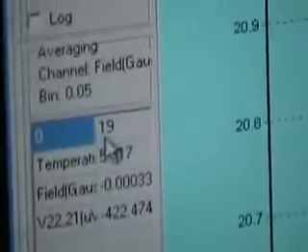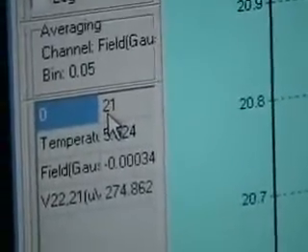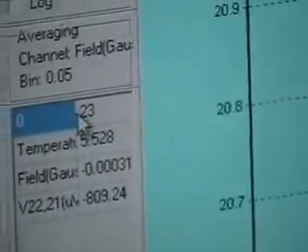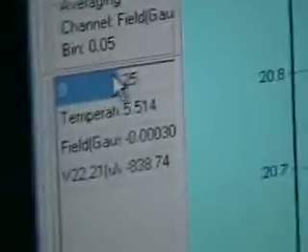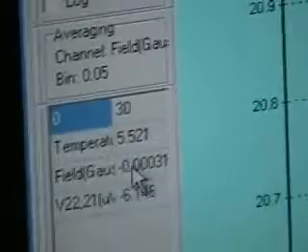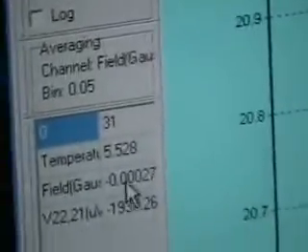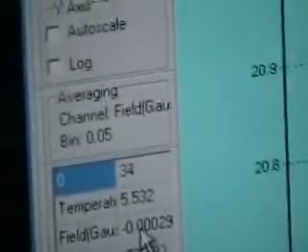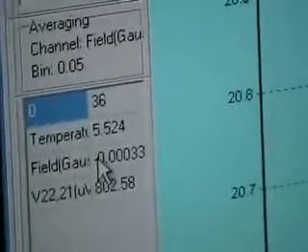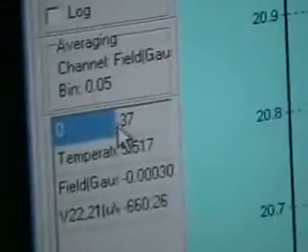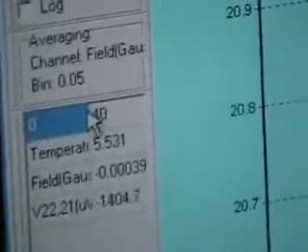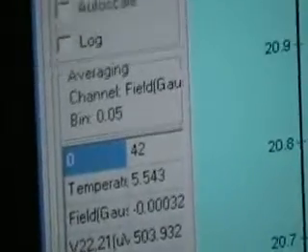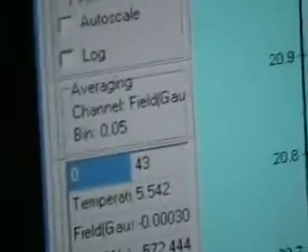So roughly every second it's taking these points, but it hasn't yet averaged them all together to form an actual data point. It would do so when the field reached some value. And since the field is static right now, it's not moving, we're never going to reach that value. But when it did, it would record 1 there, and this would be set when counted again. All right. So stop on here.